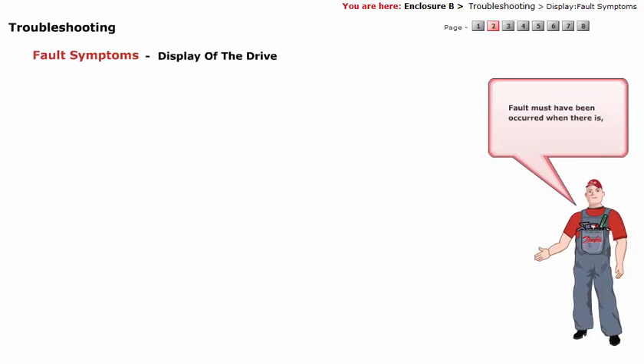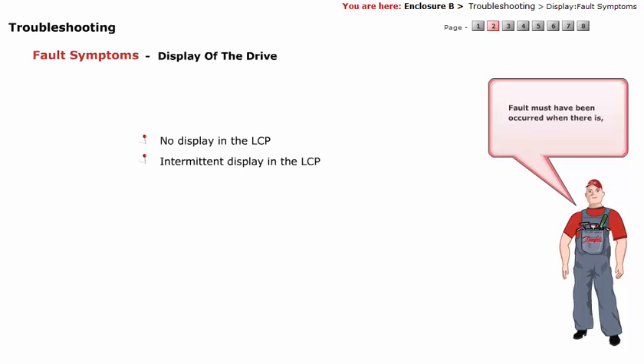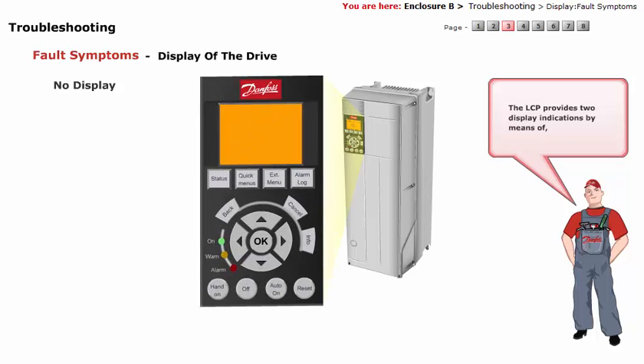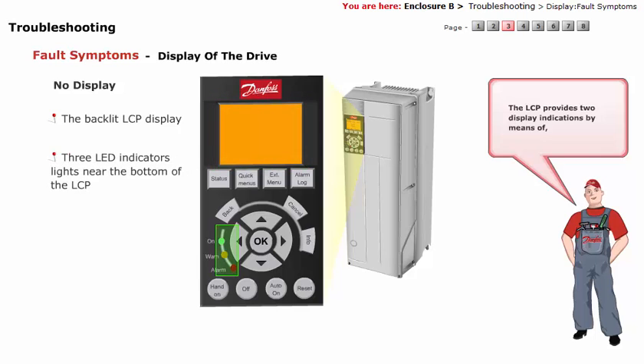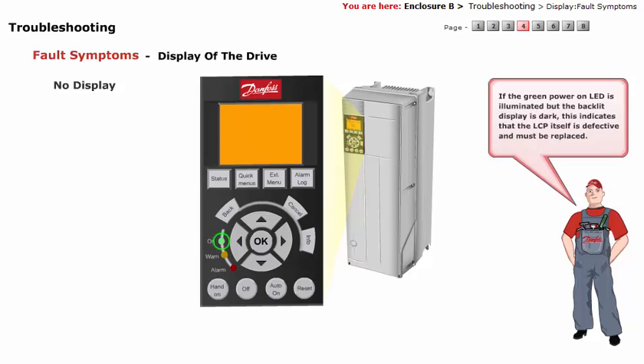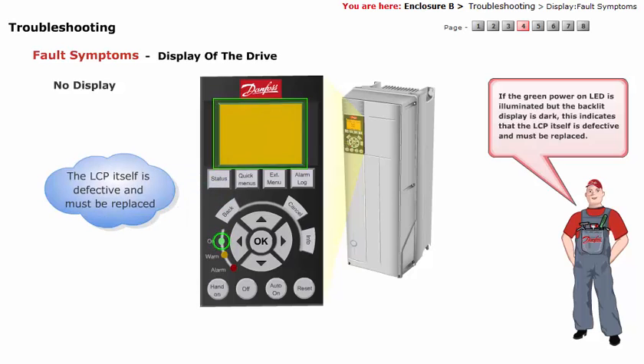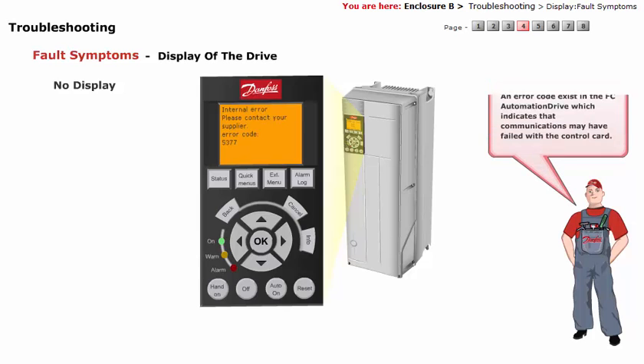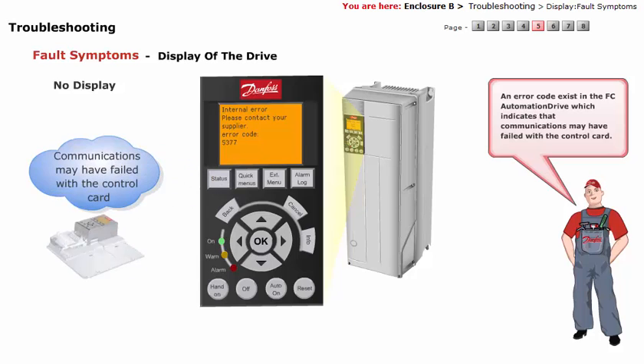A fault must have occurred when there is no display in the LCP, or there is an intermittent display. The LCP provides two display indications by means of the backlit LCP display and three LED indicator lights near the bottom of the LCP. If the green power-on LED is illuminated but the backlit display is dark, this indicates that the LCP itself is defective and must be replaced. It should be certain that the display is completely dark.